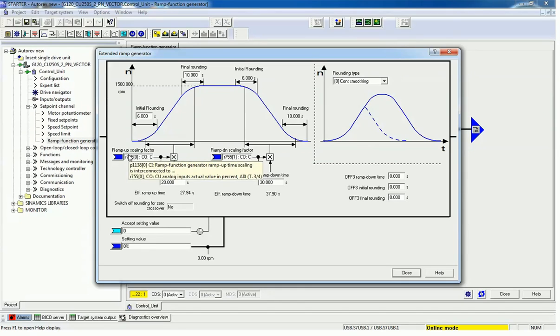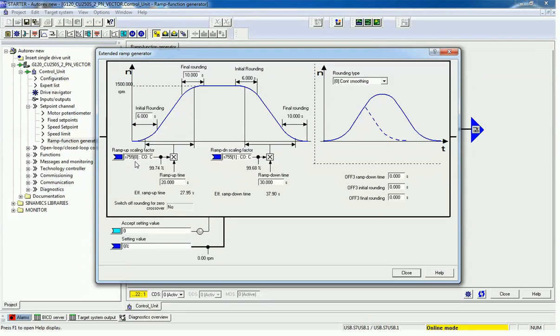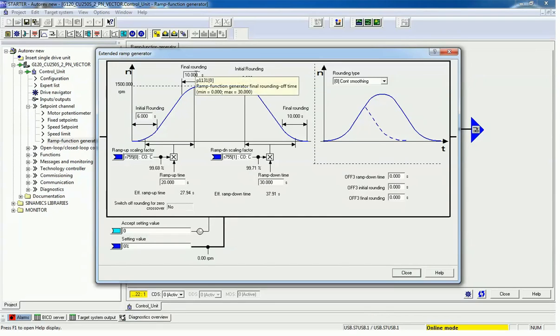You can assign a ramp up scaling factor and a ramp down scaling factor using an analog input. As per the analog input, you can assign ramp up and ramp down time. According to the percentage of that ramp up scaling factor and ramp down scaling factor, the speed will vary, and using initial rounding and final rounding we can ultimately remove the jerk from the load.